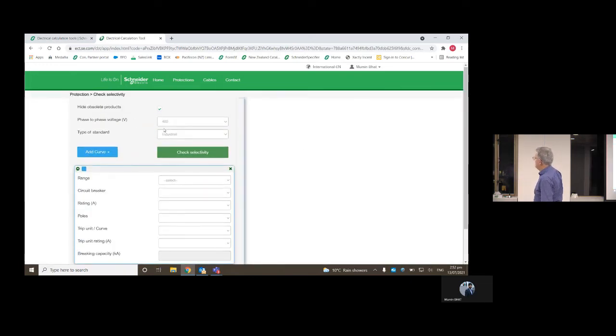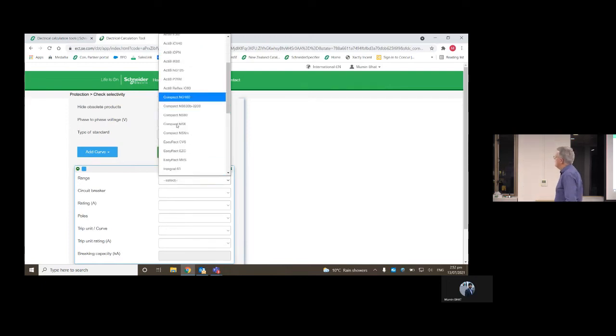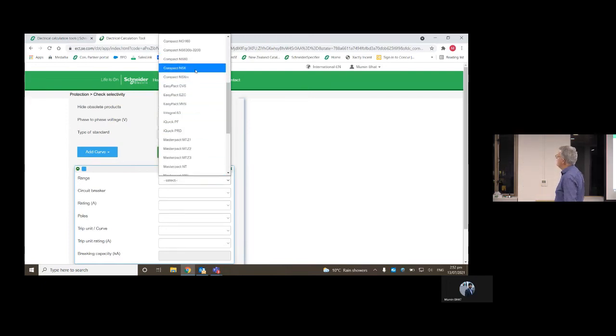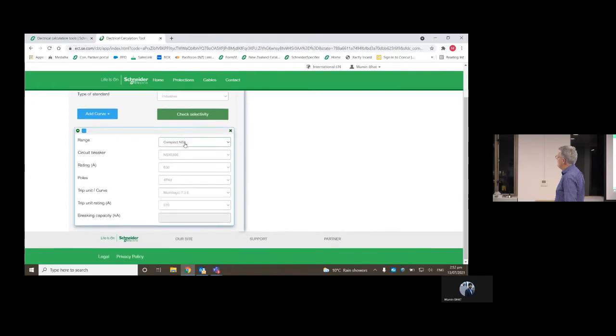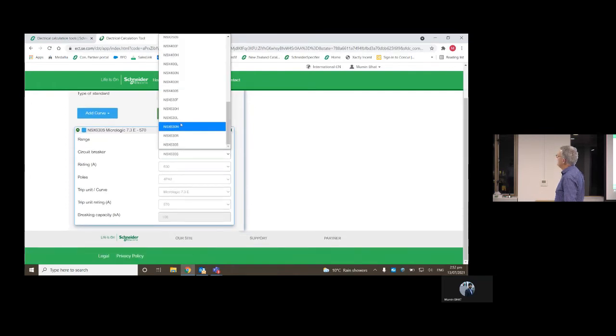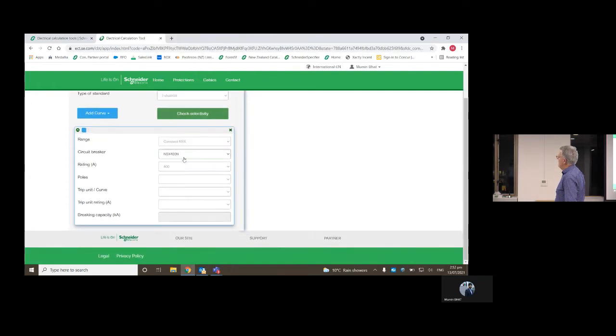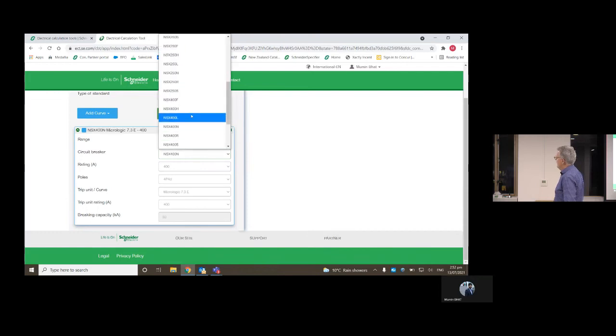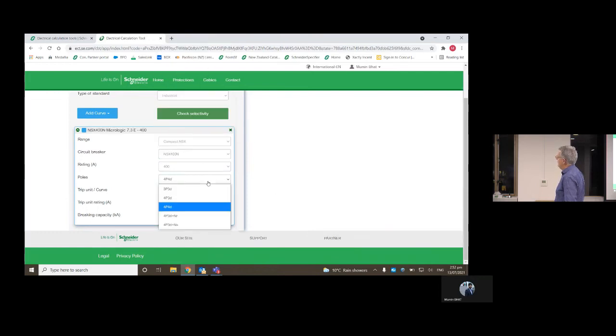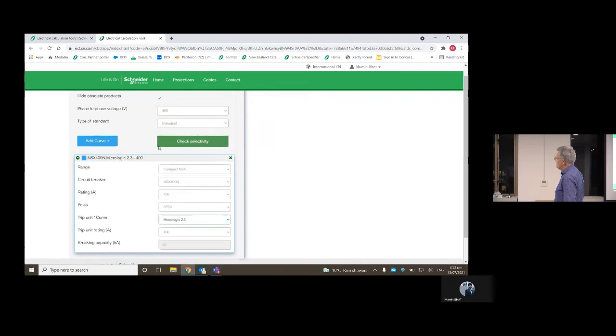So let's choose some breakers. First one we're going to choose is an NSX 400, I think. Yeah, 400N. And then we're going to change to a 3-pole. We're going to change the trip unit to a 2.3. That's a base level electronic trip unit with 2 protection settings.